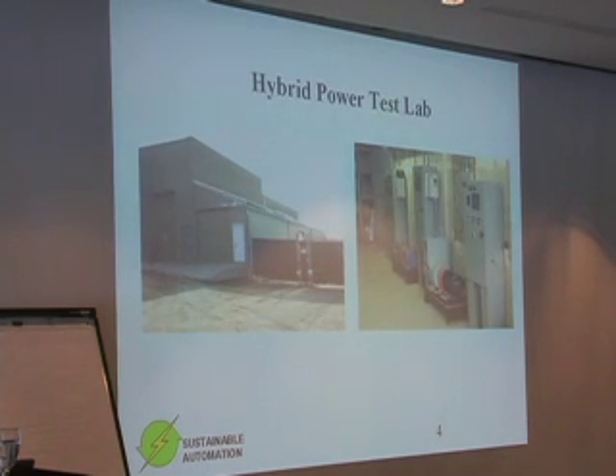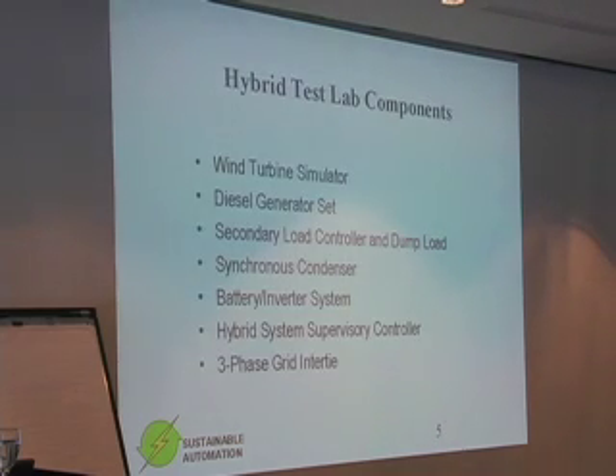Here's just a shot of our lab and test facility. Some of the components we have installed there. What we're trying to do is create a test environment that, even though it's at a relatively small scale, is representative of the systems that we encounter in the field. It's a little bit difficult to have a working wind turbine on site, so we have a wind turbine simulator that's an induction generator driven by a torque-controlled variable speed drive that allows us to feed in computer files of either power time series or wind speed time series data, which will then do the appropriate conversion and allow that machine to simulate what the actual fluctuating turbine output would be.